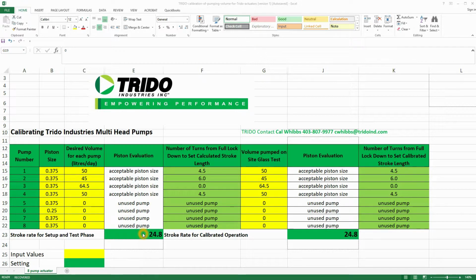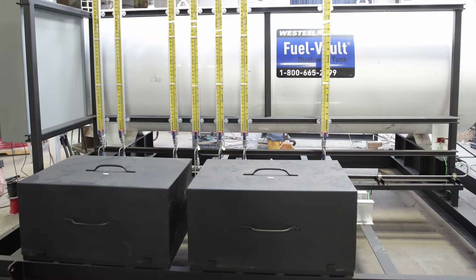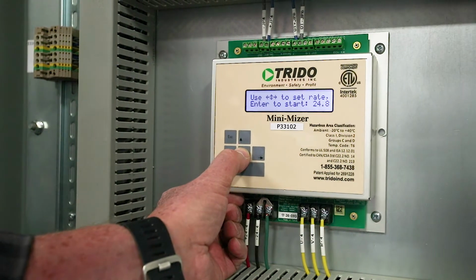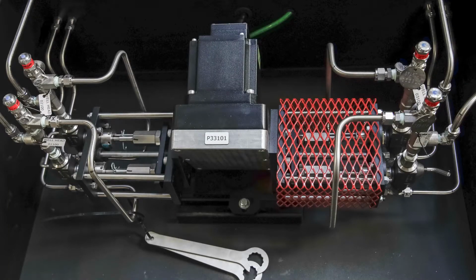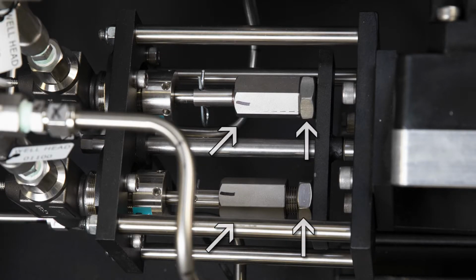Next, compare the initial stroke rate with the calibrated stroke rate. If the stroke rate has changed, the pump control panel will need to be updated to this new calibrated stroke rate. At the pump skid, adjust the pump speed controller if required. Adjust the individual chemical pumps if the required number of turns on the adjustment nut has changed.